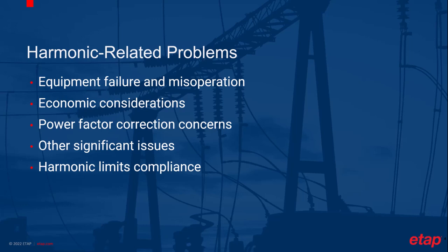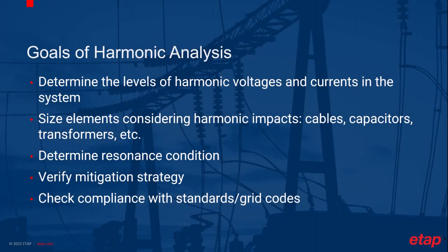And as renewable resources are growing substantially, it brings a lot of harmonic sources into the power system. Harmonic analysis, without a doubt, is an essential part of the interconnection study for renewable projects. Here are the goals we use ETAP to achieve by performing harmonic analysis. We determine the levels of harmonic voltages and currents in the system. Size the elements considering harmonic impacts, such as cables, capacitors, transformers. We determine the resonance condition, and then verify the mitigation strategy. Finally, we check the compliance against the standards and the grid codes.